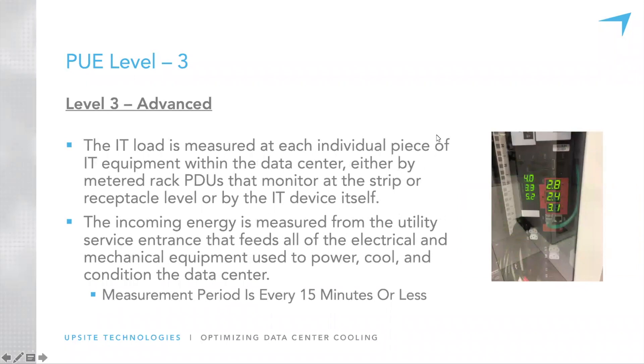PUE Level 3 is what the Green Grid considers advanced. The IT load is measured back to the power distribution units or power strips within the rack. Through our DCIM solution, we can see what our load is there. PUE Level 3 is essentially real-time, constantly measuring that load and allowing you to see where you are minute by minute.